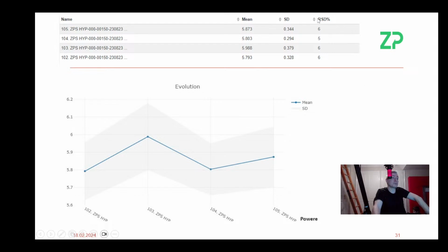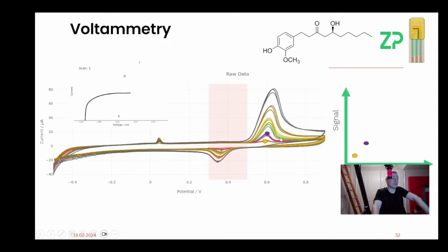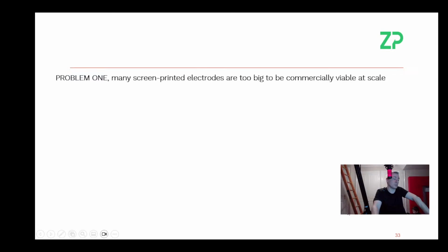And what we're looking for is to make sure that our relative standard deviations are kind of in single digit. It's a bit of a rule of thumb that if your final assay can have a relative standard deviation within 20%, then it's not a bad assay. I know it can depend on the application, but here we're showing that we can. You want your underlying electrodes to have a good repeatability, which is something that we've really worked upon, and we characterize it before we actually ship. So when you look at these, they are different concentrations done in triplicate, and they're really tight. Every triplicate is really close, some of them are overlaying, and at least the third one is pretty close, and that's the underlying screen printed electrode for you.